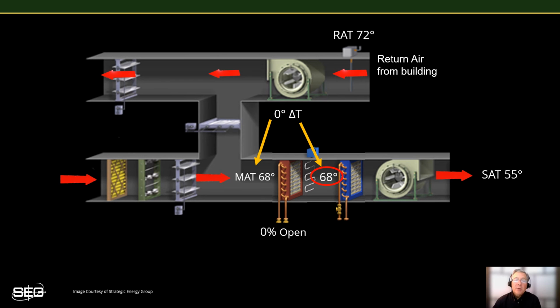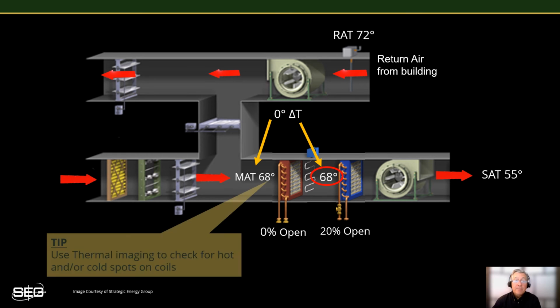Now, in this example, the valve has been repaired. We can see that by eliminating the leakage, the cooling load has been substantially reduced. Note the cooling valve has backed off to only 20%, and the cooling load has dropped, thus saving cooling energy, as well as reducing the heating energy that was also being wasted. And as a result, now more cooling capacity has been freed up to be available for handling the real cooling loads that the system was designed for.